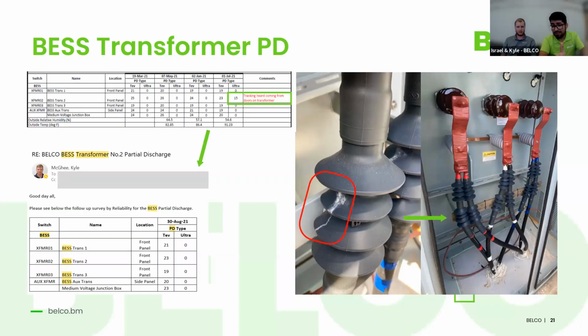So immediately, the first thing you could see is that we have those signs of corona, of partial discharge. You have that white, fibrous, powdery substance. The other thing that was immediately noticeable is that the fastening of the whole connection was a bit odd. Everything was rigidly fastened against the earth frame, and you could see that the insulators were deformed more than they probably should be.